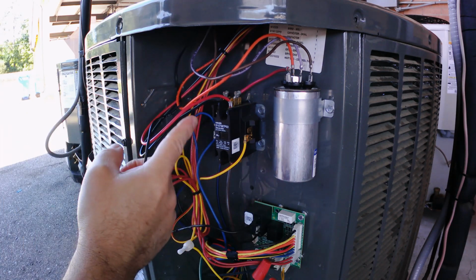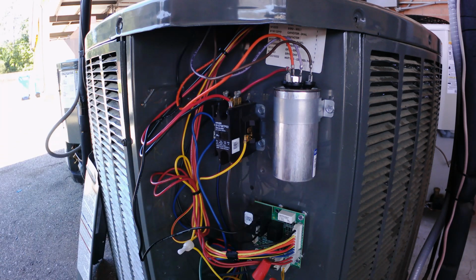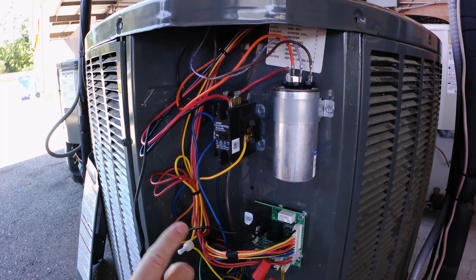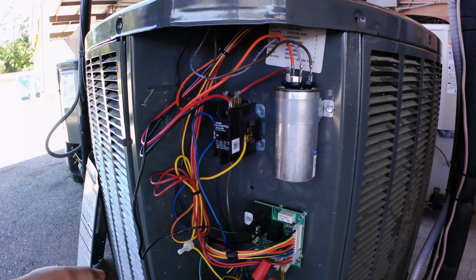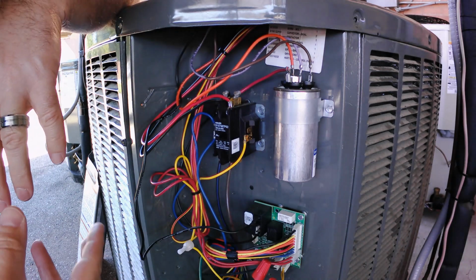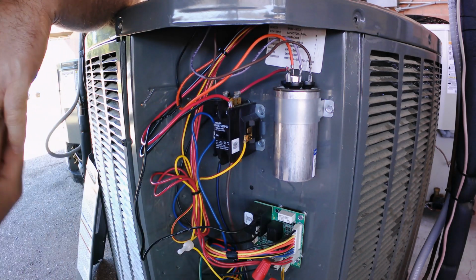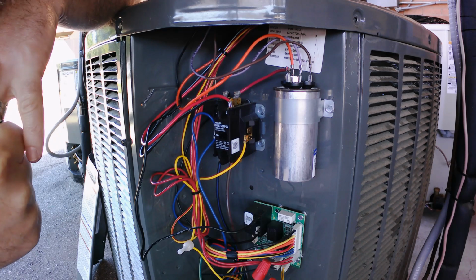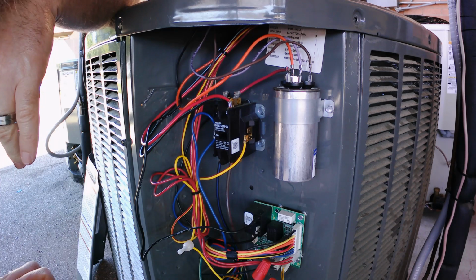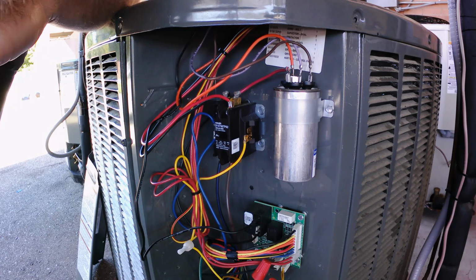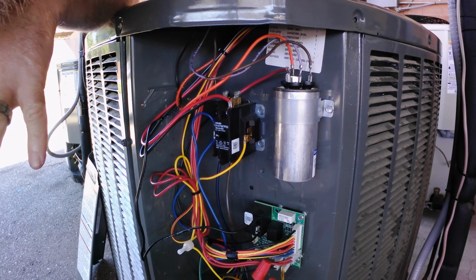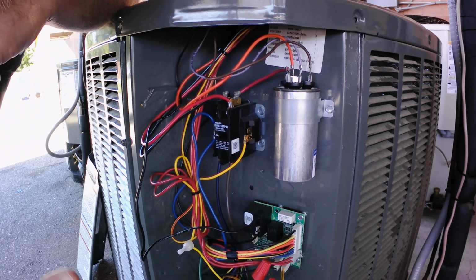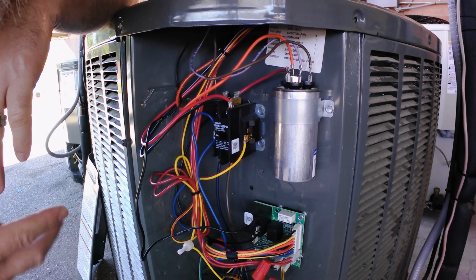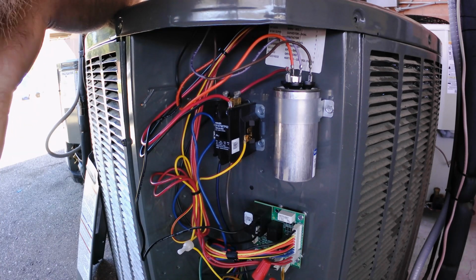It's just that this contactor only has a normally open switch. It's not like a relay, which can have a different setup as far as normally open, normally closed switches. But that's what I would do. Check the sides. If I have power there, then I'm going to ohm out the coil and then proceed with the troubleshooting steps. If I do not have 24 volts, then you have to remember that the thermostat sends power to the coil, then the coil is going to energize and move the switch, then the switch is going to have to pass your high voltage power to whatever motor, compressor, outdoor fan, indoor fan, whatever you have. Even heat strips, the principle is still the same.